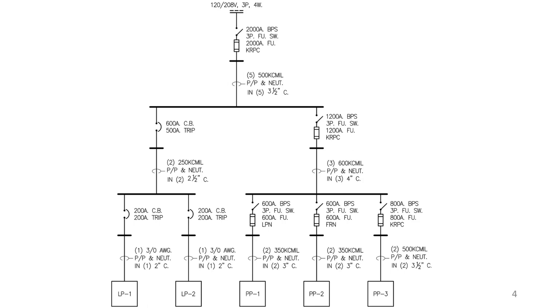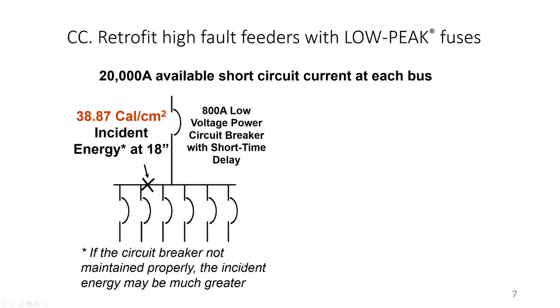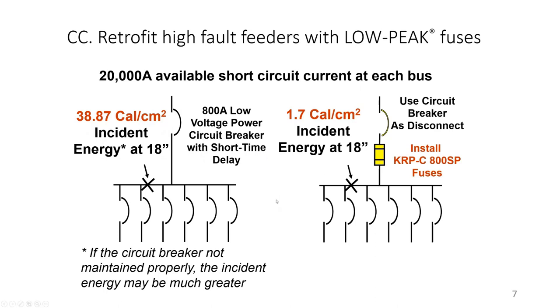Now, the issue is, now that we are becoming slowly more and more conscious about arc flash safety hazards, to lower those, the solution in some cases is going to be a circuit breaker, in particular when you have a low fault current. I'm going to jump ahead for a second into this slide, and I'm sure a lot of you guys have seen it. This is how the fuse manufacturers are going to sell us their product. And I'm not mocking anything, but I'm pointing out that in some cases it's not the answer, because you also need, as much as you need to understand the operation of the fuse, okay, it's going to be current limiting dramatically to reduce the arc flash incident energy at the panel board. At the same time, it's not going to react fast enough if the available fault current is low.